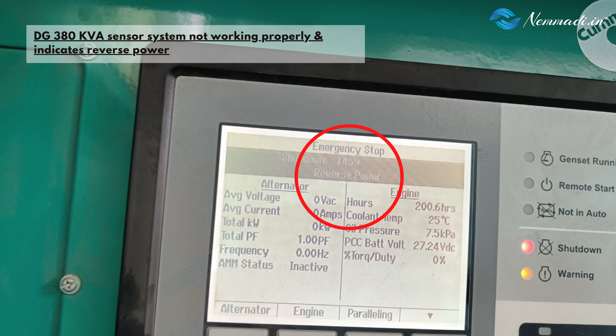This is another classic case of negligence. There are three generators working, and one of them is not pumping out the power required. Instead of pumping out power, it is drawing power and working like a prime mover. Needless to say, if not attended to immediately, the coil of that generator is going to burn out.